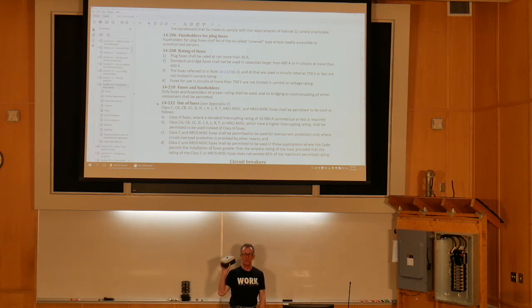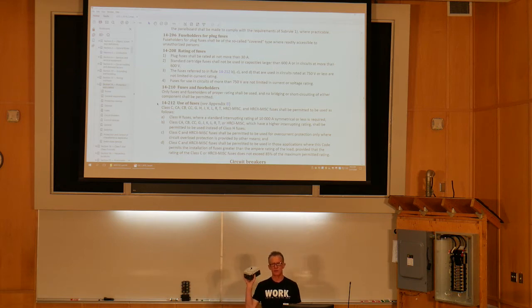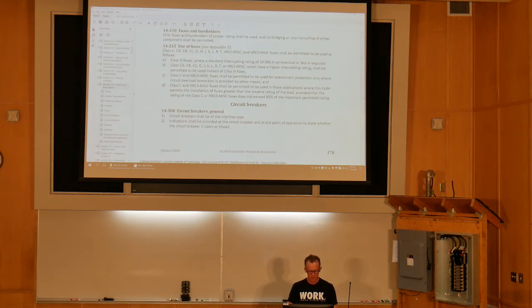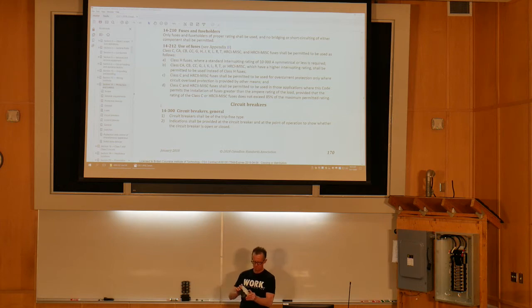Alright, so now here we have a molded case circuit breaker, and let's look at our circuit breaker rules. 14-300, Subrule 1: Circuit breakers shall be of the trip-free type. What does that mean? Here, circuit breaker, off position, I turn it on. Even if I put a broom handle under this thing to hold it on, the breaker would still trip under overcurrent or overload. That is what trip-free means.